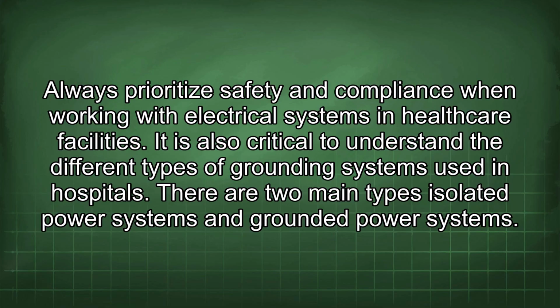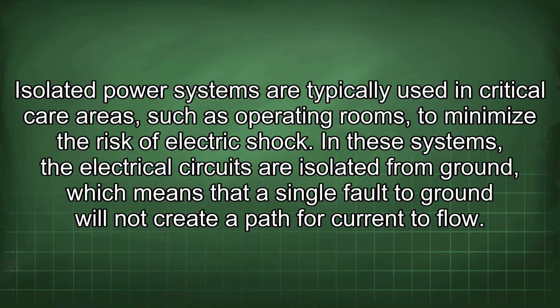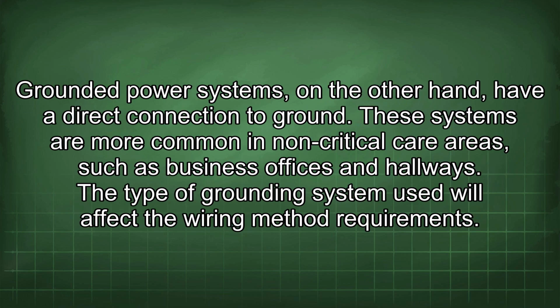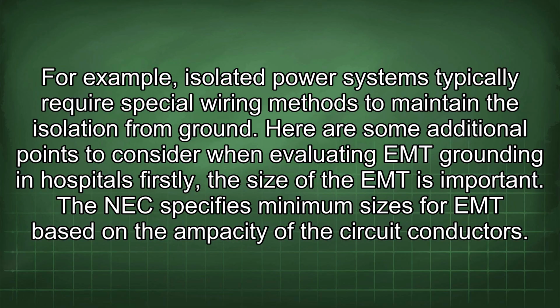It is also critical to understand the different types of grounding systems used in hospitals. There are two main types: isolated power systems and grounded power systems. Isolated power systems are typically used in critical care areas, such as operating rooms, to minimize the risk of electric shock. In these systems, the electrical circuits are isolated from ground, which means that a single fault to ground will not create a path for current to flow. Grounded power systems, on the other hand, have a direct connection to ground. These systems are more common in non-critical care areas such as business offices and hallways. The type of grounding system used will affect the wiring method requirements. For example, isolated power systems typically require special wiring methods to maintain the isolation from ground.